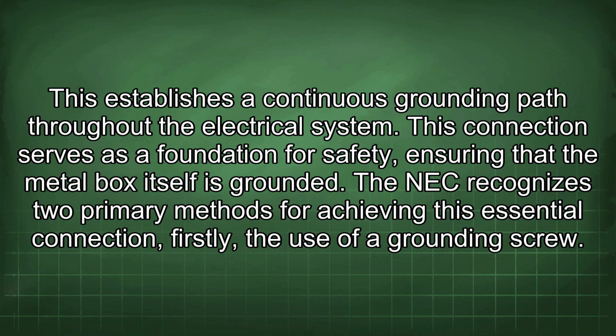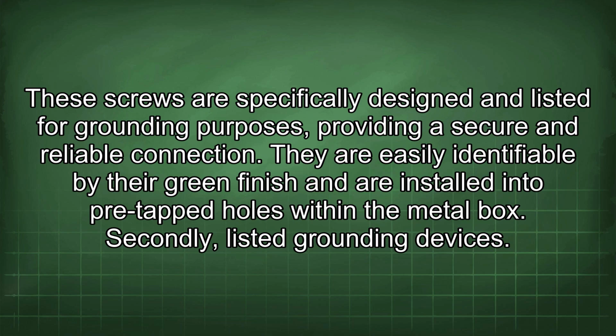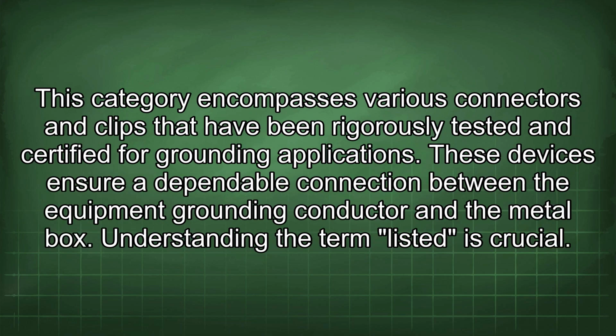Firstly, the use of a grounding screw. These screws are specifically designed and listed for grounding purposes, providing a secure and reliable connection. They are easily identifiable by their green finish and are installed into pre-tapped holes within the metal box. Secondly, listed grounding devices. This category encompasses various connectors and clips that have been rigorously tested and certified for grounding applications. These devices ensure a dependable connection between the equipment grounding conductor and the metal box.